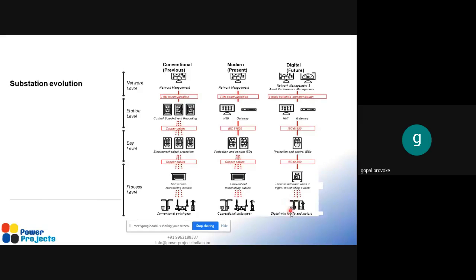So the space requirement has been reduced here when we use non-conventional instrument transformers, digital or non-conventional. For transmitting the current and voltage signals to the protection relays, we need protection relays for protecting equipment like transformers and bus bars. So we have various protections: over current, over voltage, under voltage, differential protection, and so on.